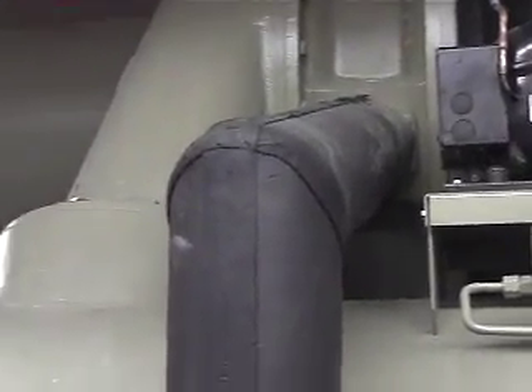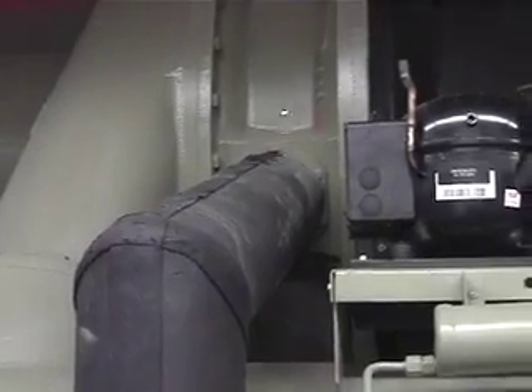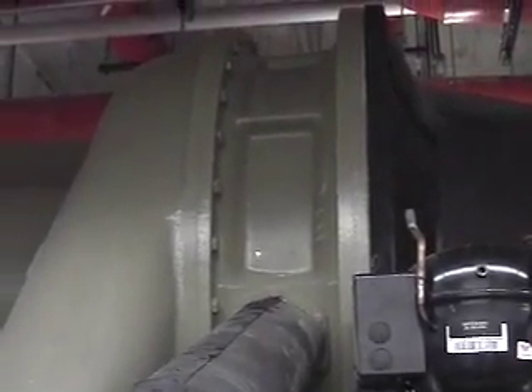There, inside right there, is where you'll see your first orifice plate to break down your refrigerant. As it breaks down, it comes through here and up and about this high into the chiller. Got another orifice plate with some screens. Comes through, comes up this line right here. Goes back into your second stage of your compressor section.